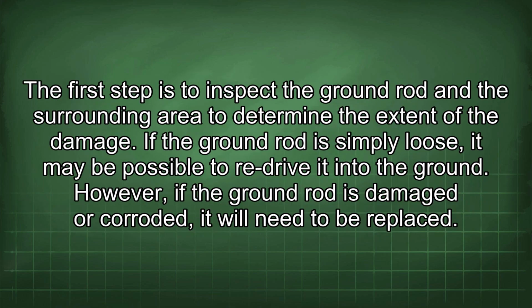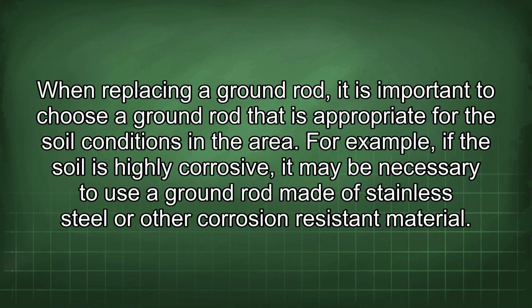The first step is to inspect the ground rod and the surrounding area to determine the extent of the damage. If the ground rod is simply loose, it may be possible to redrive it into the ground. However, if the ground rod is damaged or corroded, it will need to be replaced. When replacing a ground rod, it is important to choose a ground rod that is appropriate for the soil conditions in the area. For example, if the soil is highly corrosive, it may be necessary to use a ground rod made of stainless steel or other corrosion-resistant material.